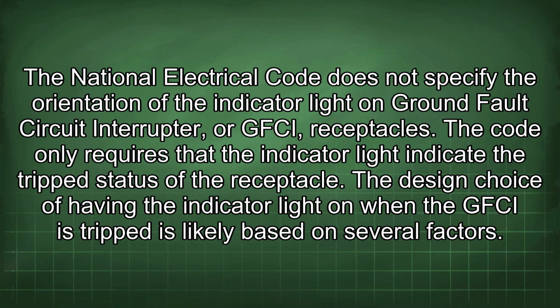The National Electrical Code does not specify the orientation of the indicator light on ground fault circuit interrupter, or GFCI, receptacles. The code only requires that the indicator light indicate the trip status of the receptacle. The design choice of having the indicator light on when the GFCI is tripped is likely based on several factors.